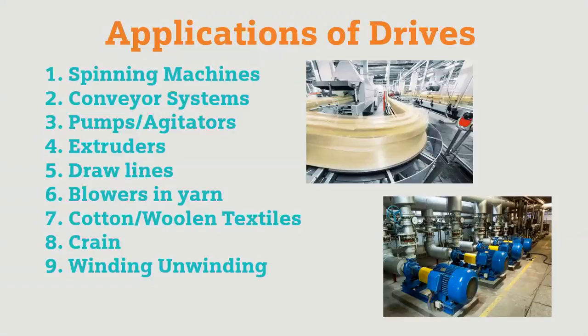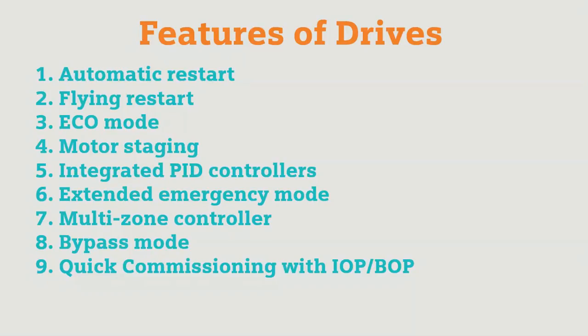There are thousands of applications in which we are using drives. Now we'll see the features of drives. Based on drive model and make, different features are available. For the Siemens AC drive, automatic restart will be activated when there is a power failure. Flying restart can be used when the inverter is connected to a running motor. ECO mode operation, motor staging for closed-loop control system, and integrated PID controllers — we can use a closed-loop control system with different variables like pressure, temperature, or flow.